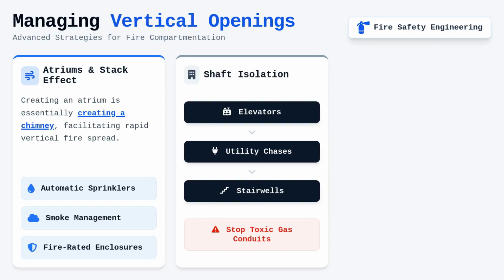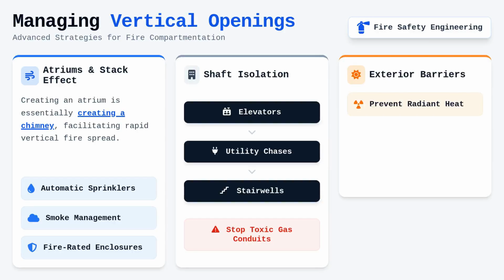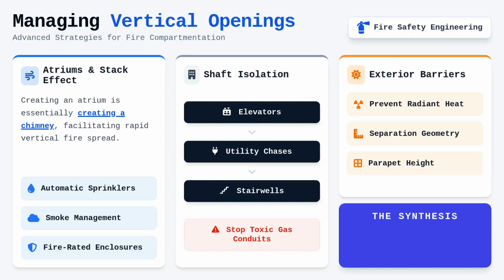gases. We calculate the allowable unprotected openings in exterior walls based on the distance between buildings, aiming to prevent the ignition of adjacent structures through radiant heat transfer. By correctly applying the geometric rules for spatial separation and parapet height, we ensure that the exterior envelope remains a reliable barrier. This is the synthesis of material science and architectural physics, aimed at containing a fire within its origin zone until it can be extinguished.